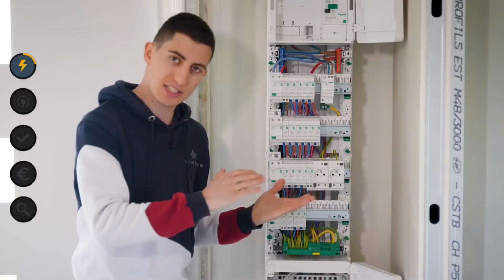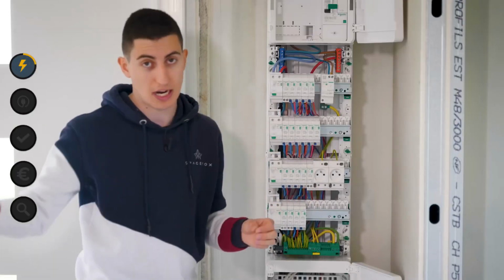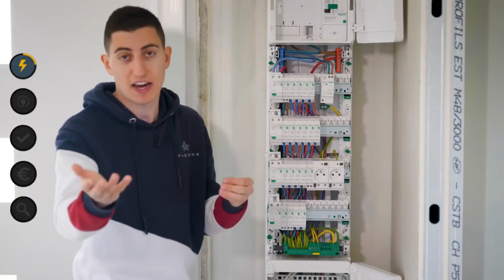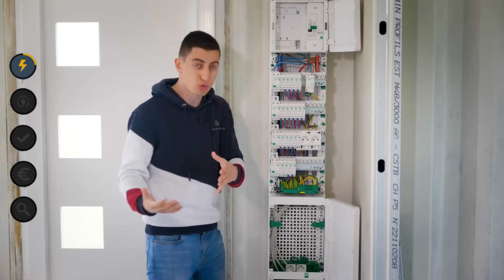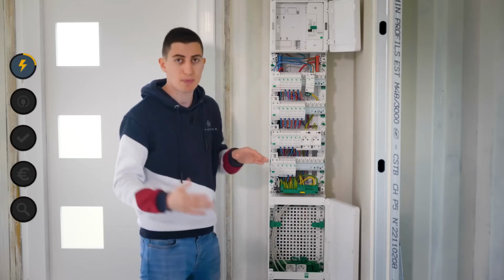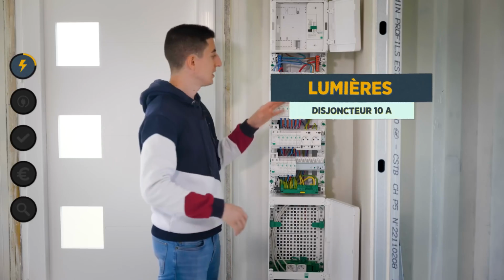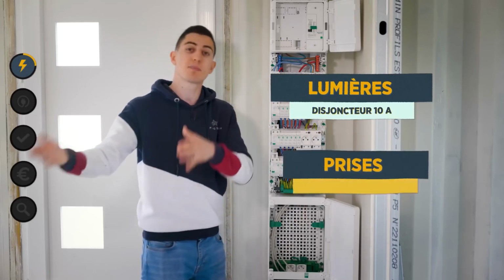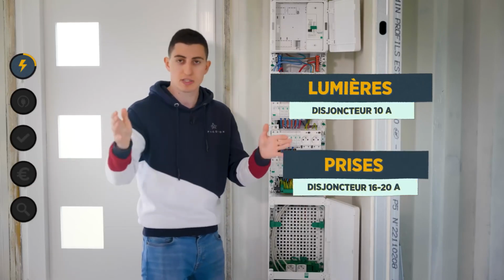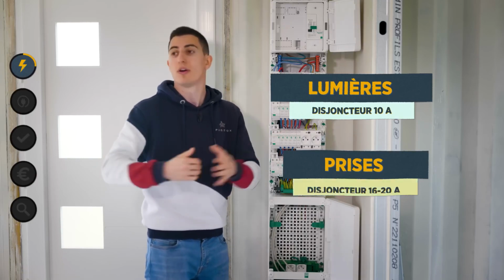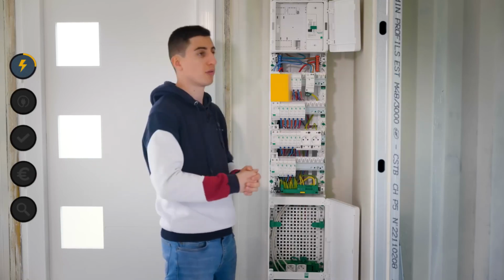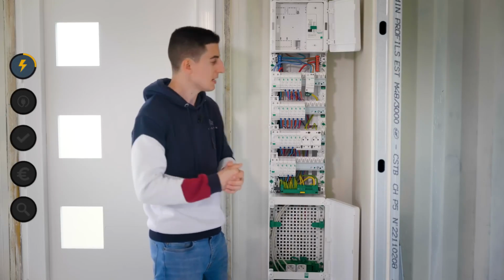To know which divisional breaker to use for which device, we refer to the NF C 15-100. For example, it's customary to use 10 ampere breakers for lights and 16 or 20 ampere breakers for power outlets. For a microwave oven, it's going to be 20 amperes, and for a fridge, it's also going to be 20 amperes.